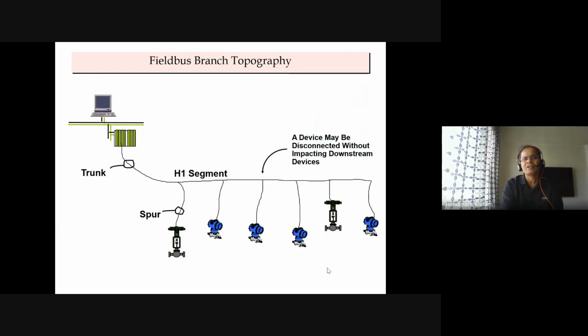So in the field bus, different topologies are used for connections. In the field bus they introduce what they call the H1 segment, meaning the H1 communication network, and one more is H2, this side they call H2. For the field devices, they call it the H1 cable, H1 communication. The cable coming from the card system to the junction box is called the trunk cable, main cable, and from the junction box to the devices, the cable is called the spur cable. This is standard terminology used in the field bus, especially in Foundation Fieldbus.